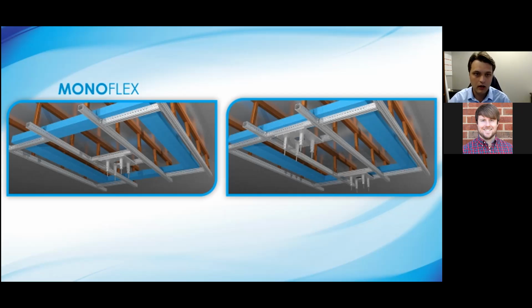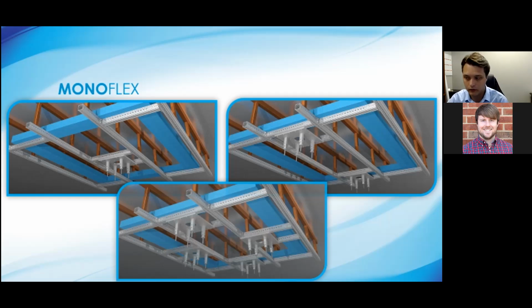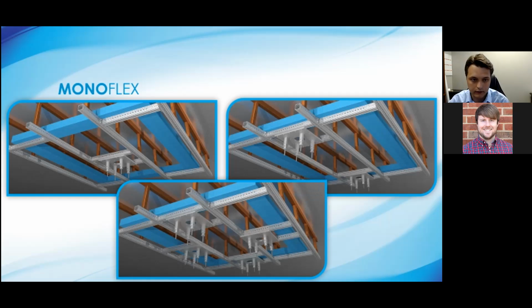Now let's take it a step further though and ask, what if 2 or 3 years down the road the ownership wants to make this operating room a full-blown operating room? It's going from a procedure room to a full-blown operating room, so they need to add 2 more booms. Normally you're talking about another renovation project. However, with this system, all you have to do is put a couple more boom plates in there, mount it to the grid that's already existing, no cutting, no welding required, and then you just rearrange the ceiling system with those individual components instead of removing an entire subsection of a plenum. This can allow you to really not have to renovate an OR for decades after the project is completed.